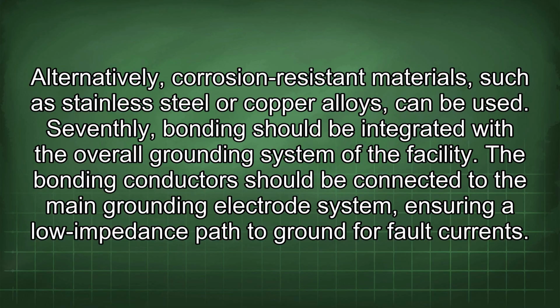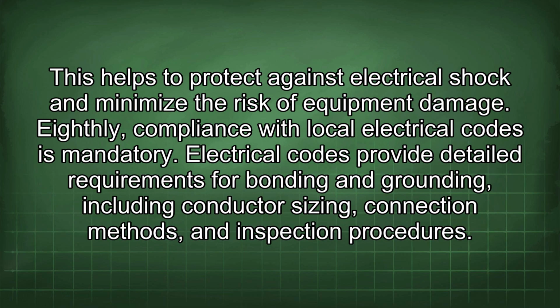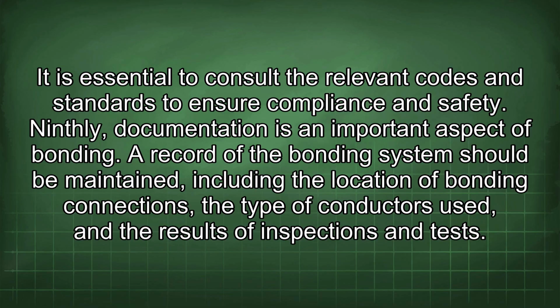Seventhly, bonding should be integrated with the overall grounding system of the facility. The bonding conductors should be connected to the main grounding electrode system, ensuring a low impedance path to ground for fault currents. This helps to protect against electrical shock and minimize the risk of equipment damage. Eighthly, compliance with local electrical codes is mandatory. The electrical codes provide detailed requirements for bonding and grounding, including conductor sizing, connection methods, and inspection procedures. It is essential to consult the relevant codes and standards to ensure compliance and safety.